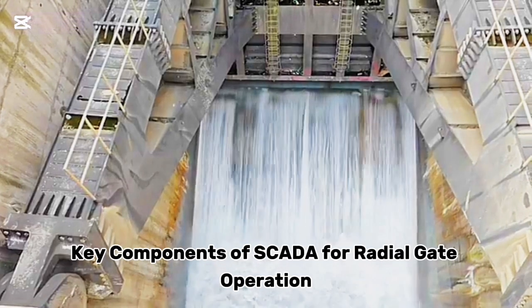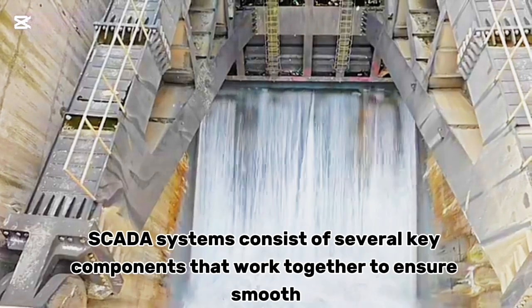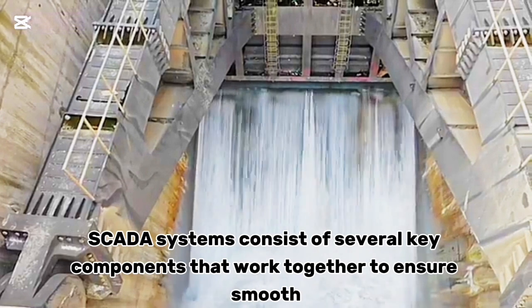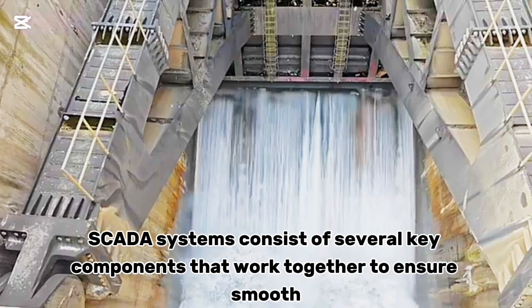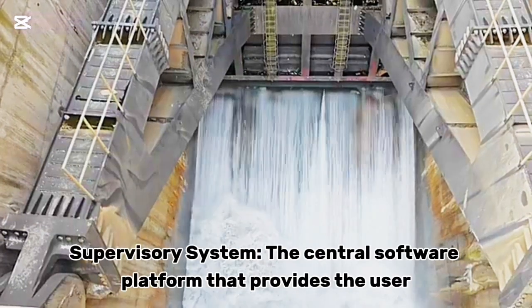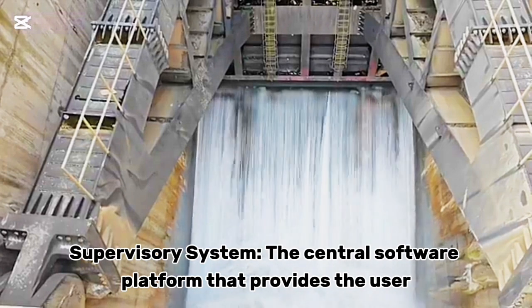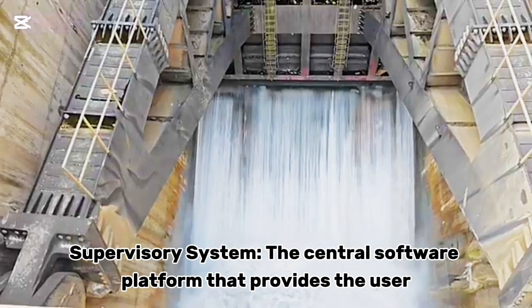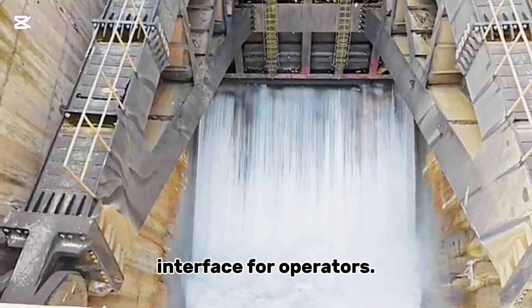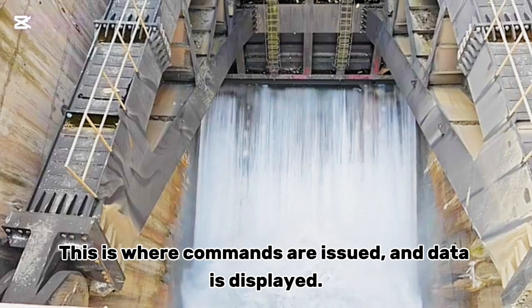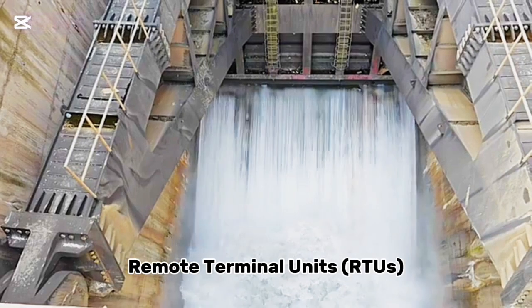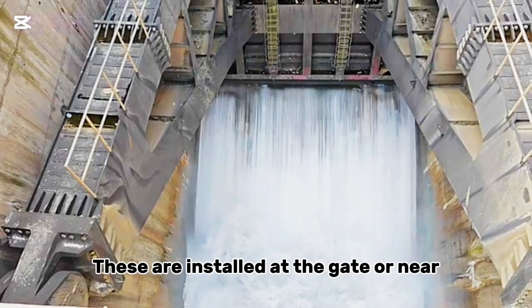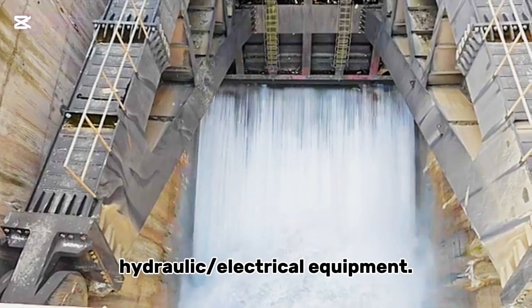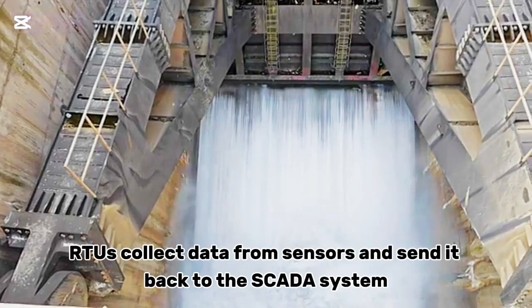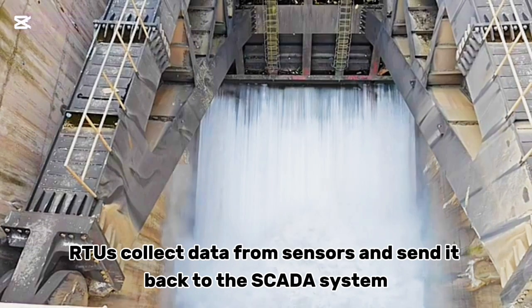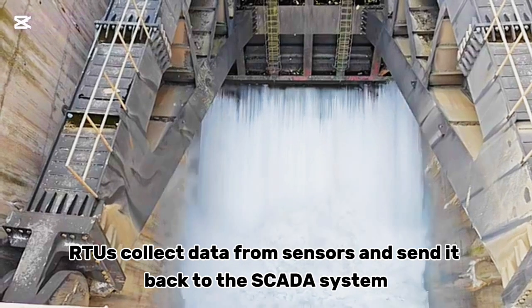Key components of SCADA for radial gate operation. SCADA systems consist of several key components that work together to ensure smooth gate operation. Supervisory system, the central software platform that provides the user interface for operators. This is where commands are issued and data is displayed. Remote terminal units (RTUs). These are installed at the gate or near hydraulic, electrical equipment. RTUs collect data from sensors and send it back to the SCADA system.